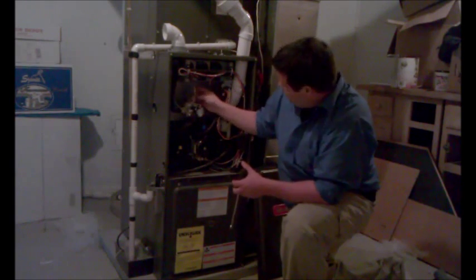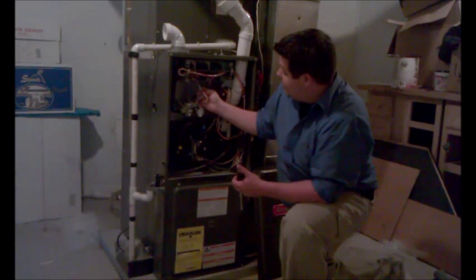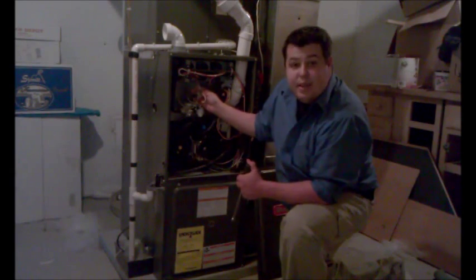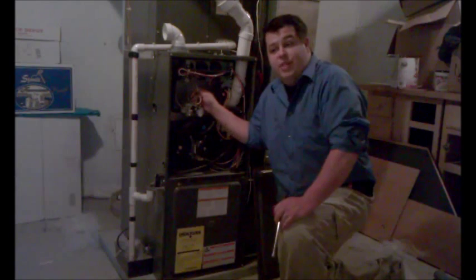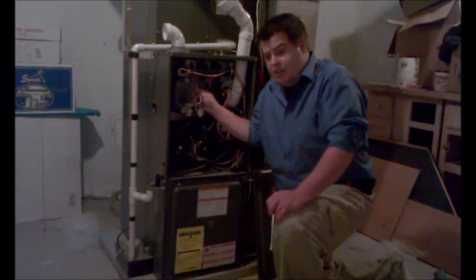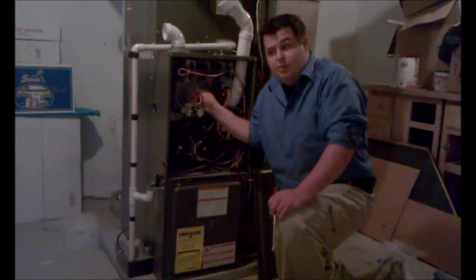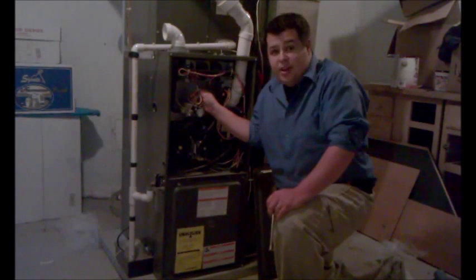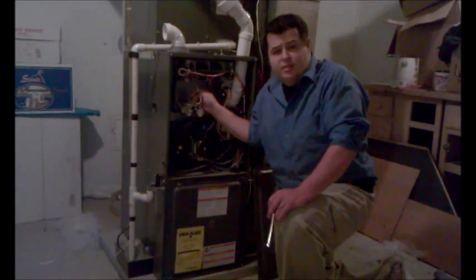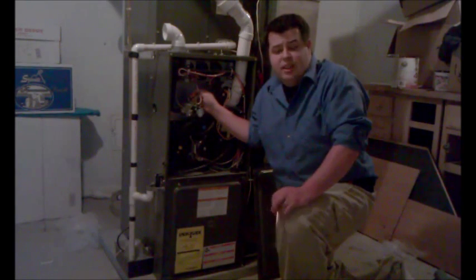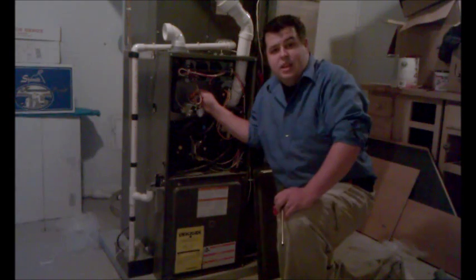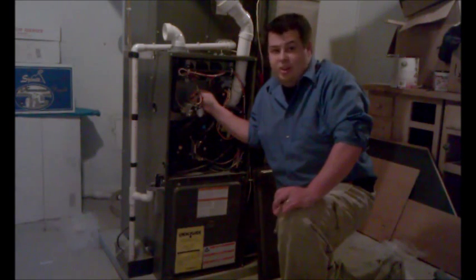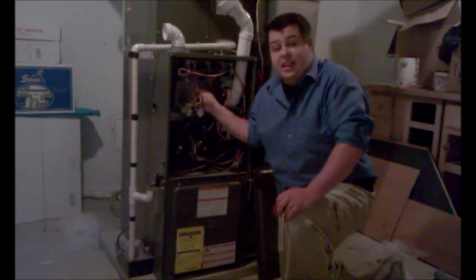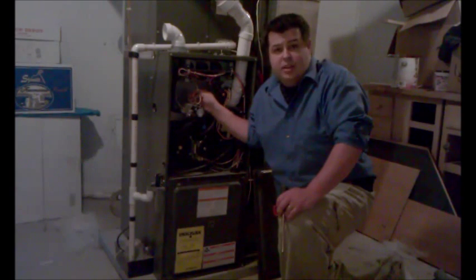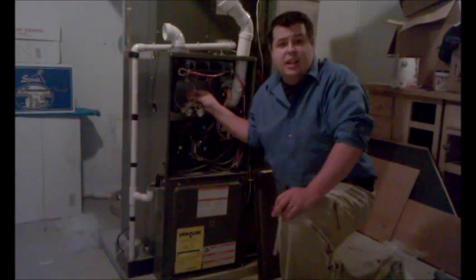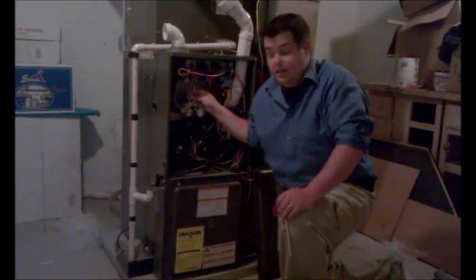The other thing we're doing is something that should be done every year as well, is cleaning the flame sensor. The flame sensor, if that's not clean, the furnace will kick on and then shut right back off again. It'll just keep doing that. Sometimes it'll do it once or twice and then kick on finally. Other times, when it gets towards the end of the flame sensor's ability to run, it'll just do that all day long and you'll never get any heat out of it. So that's important to be cleaned every year, so you don't end up on a cold day or a cold weekend and not have any heating.